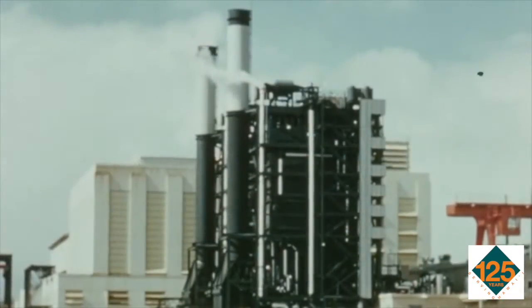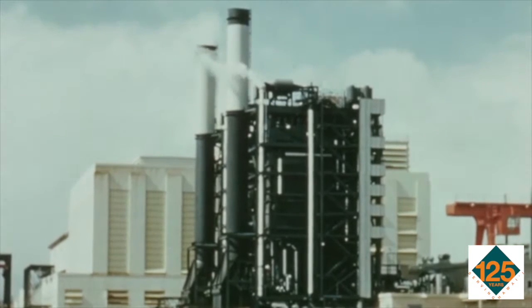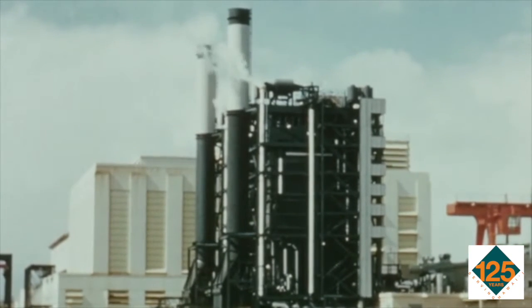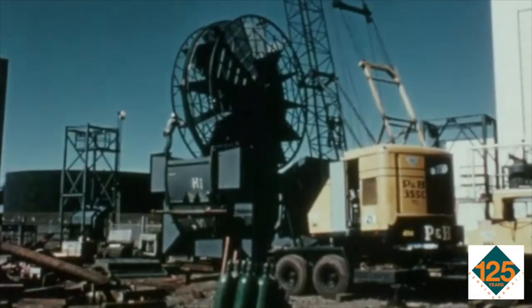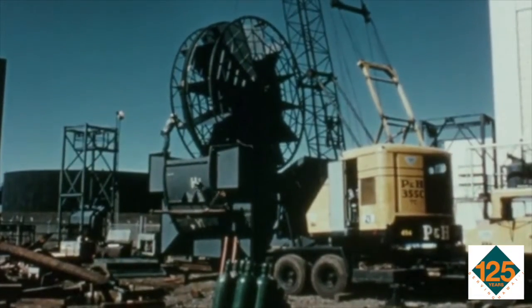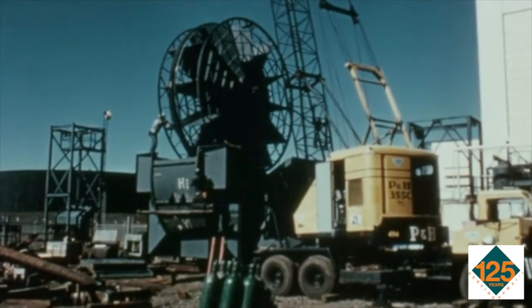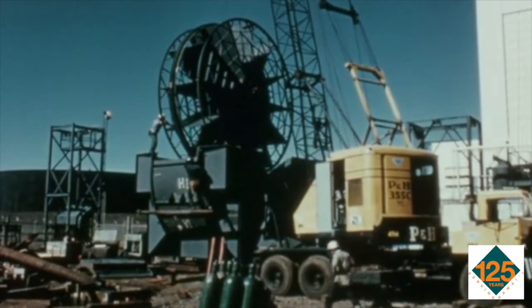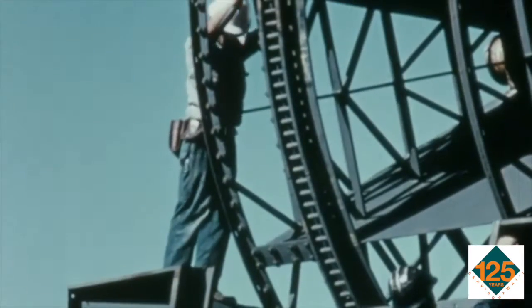The 1,200-ton boiler is supported from the top of the steel frame, and provisions are made to allow for expansion when it is heated to operating temperature. Even the waste gases from the fuel burned to heat the boiler are put to use. They are passed through an economizer and an air heater to heat the incoming water and also heat the air for combustion in the burner.